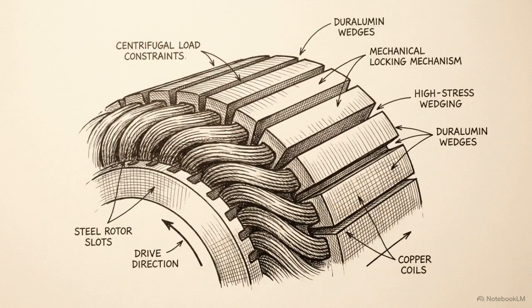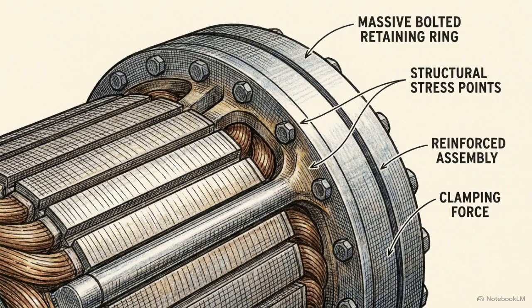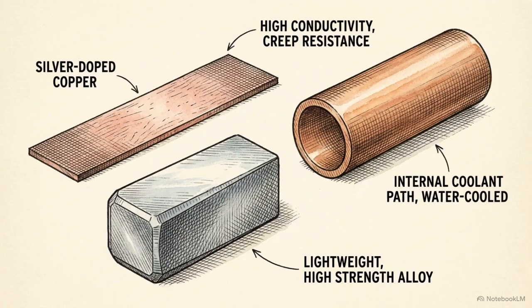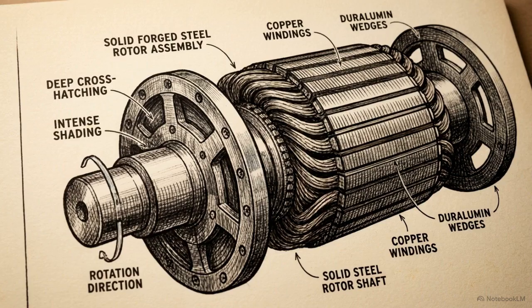To prevent the silver-doped coils from tearing outward under centrifugal load, they are secured in the body slots by duralumin wedges, locked down by heavily reinforced retaining rings at the end portions. Every material, from the silver-doped copper to the duralumin wedges and hollow stator bars, is selected specifically to allow the core to survive its own violent electromagnetic and rotational forces.